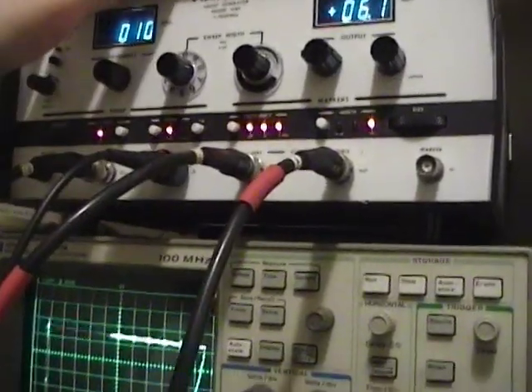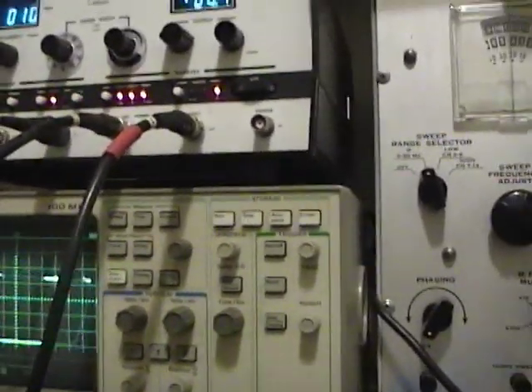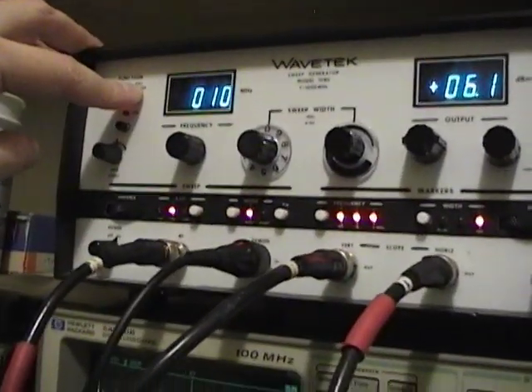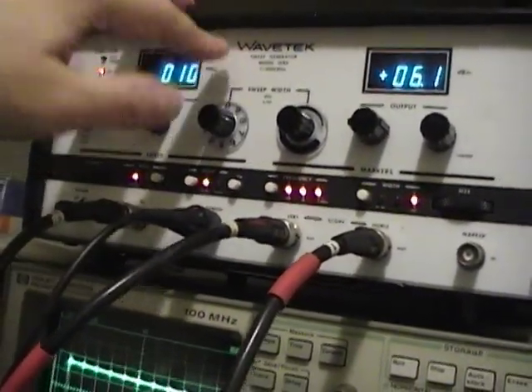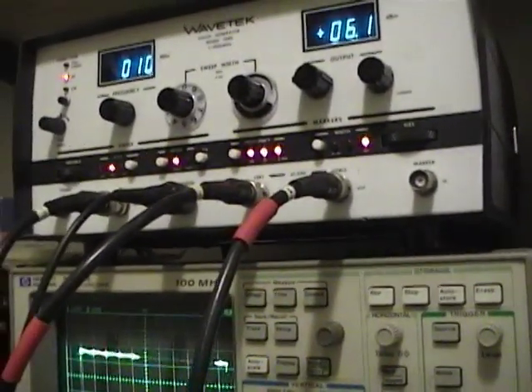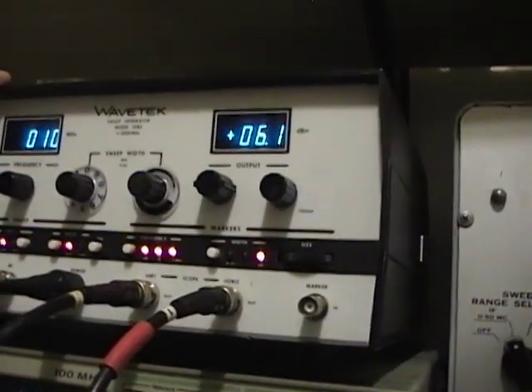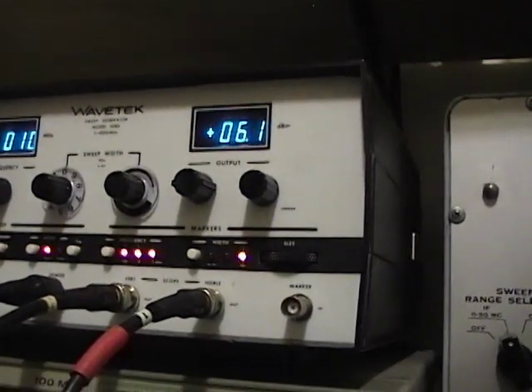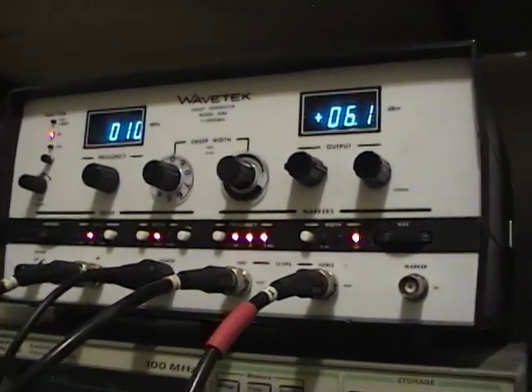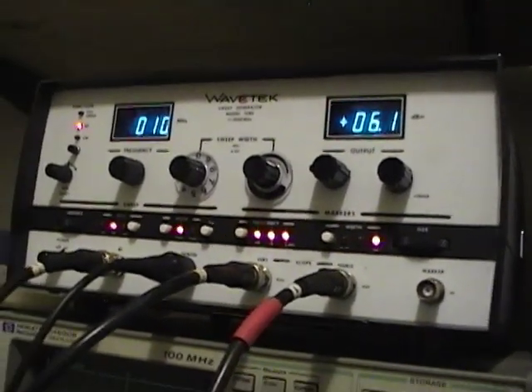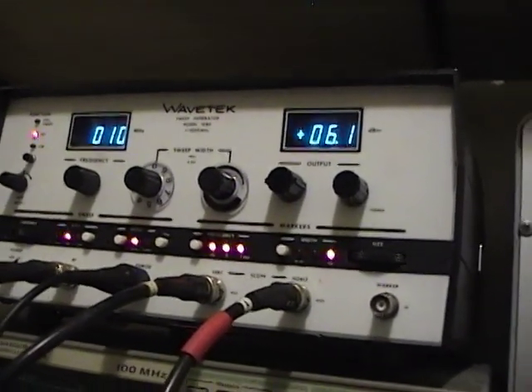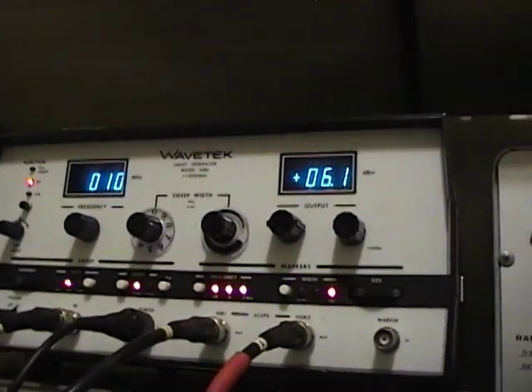And that is why I'm going to be using this over these other older devices. This last mode, full sweep, that will sweep from zero to one gigahertz, which I can't imagine I would ever do. This is a general purpose device, and I think one of its applications is for like the cable TV industry where you very well may want to see how well signals transmit from the full zero to one gigahertz. Cable TV uses quite a bit of bandwidth on that coax cable.